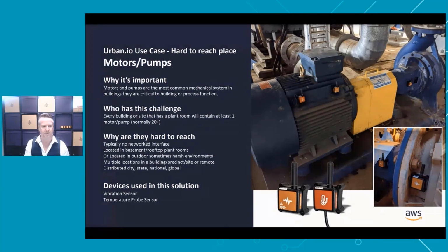Motors and pumps are a massive challenge everywhere. There are literally millions of electric motors, and probably a lot of them connected to gearboxes and pumps, that are not monitored - they don't have telemetry in them traditionally. So being able to retrofit on, we use a combination of a vibration sensor and a temperature sensor to get that combination of temperature and vibration. There are lots of sensors like this around the world, and I think most control systems have started cottoning onto this. However, none that we can find will connect over multiple kilometers or miles away from the connectivity point, so we feel like we've found a pretty big niche.